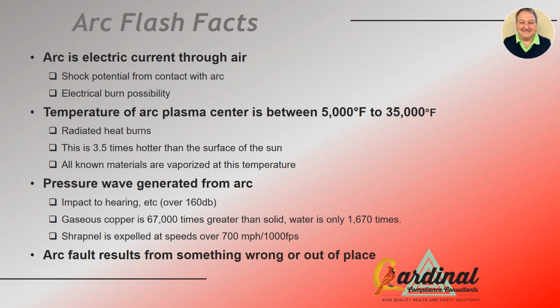We also have things that start to fly out of the panel at us. We have melted metal. We have pieces of copper, be it the bus bar or wires or other devices that were in there that are in the arc, that is the path of heating, current flow. Also, we get shrapnel accelerated out of that panel. We have a large amount of air pressure because of the expanding heat that helps motivate or push these things out of there. It's not a common everyday occurrence, but when it goes bad, it goes bad.